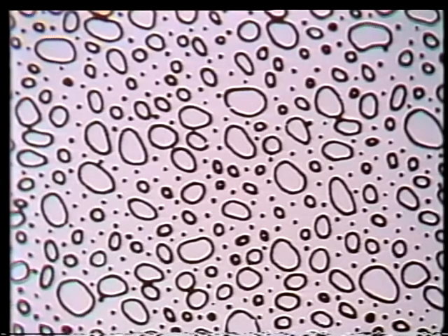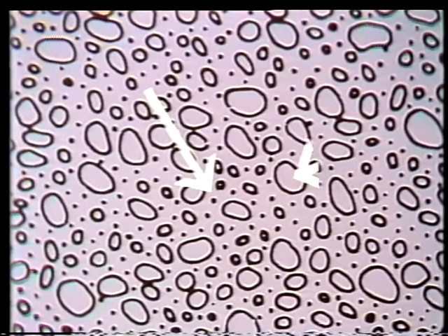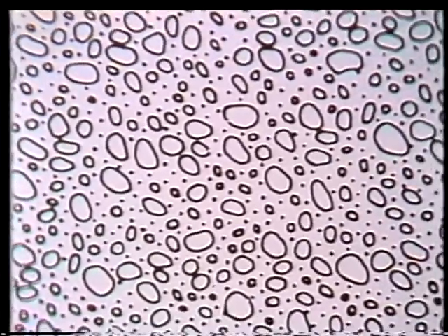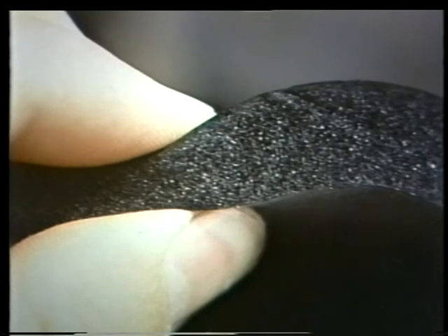Mass-type insulation combines these two elements into one: a material that's a relatively poor conductor of heat and dead air trapped in pockets within the material. The effectiveness of mass-type insulation depends largely on the amount of air trapped in the material. If the insulation is compressed, some of the air is forced out, reducing its insulation value. The same thing happens if the insulation gets wet.